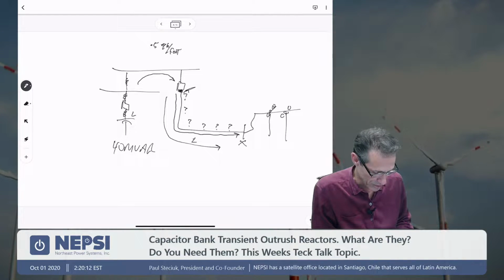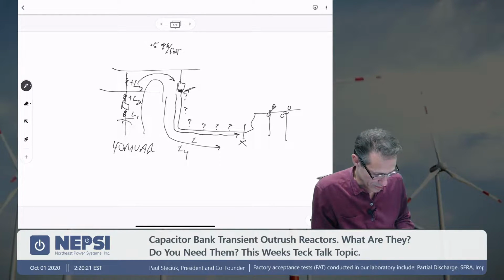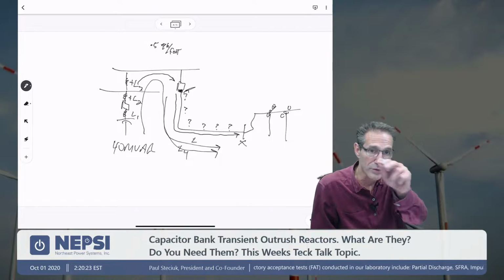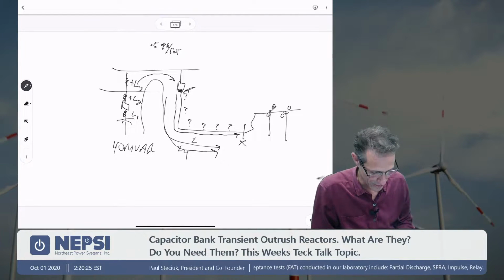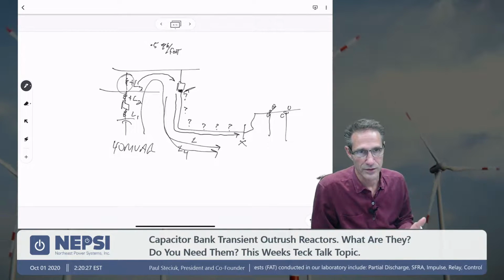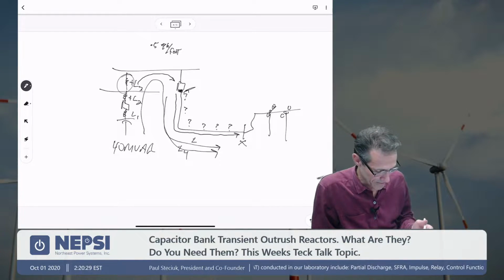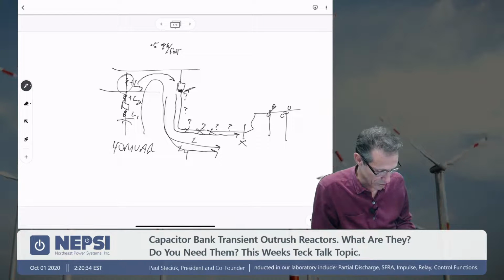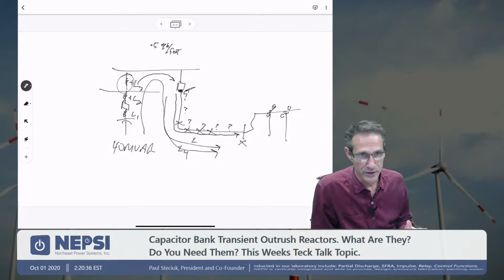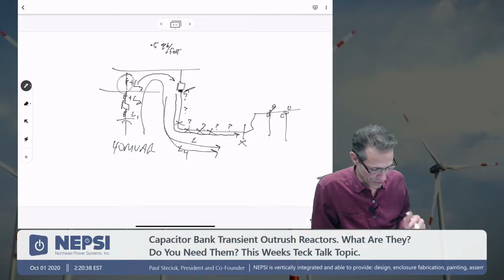So the inductance here is L1 plus L2 plus L3, and then plus L4. That total inductance might be enough that you don't need this, and that's really the thing to evaluate. What is the possibility of a three-phase or phase-to-phase fault along this length? If it's cable, it's very low.